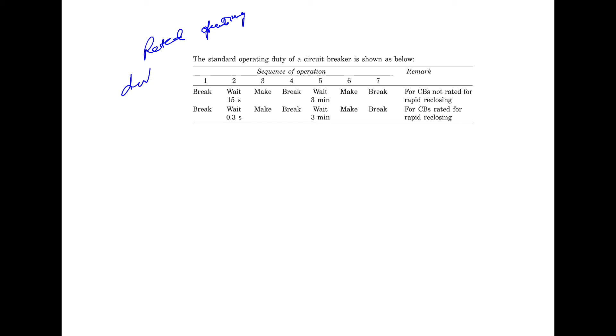Now the standard operating duty of the circuit breaker is shown here. First is break. This is for the circuit breakers not rated for rapid reclosing. What is the sequence of operation? It breaks, waits for 15 seconds, then it will make again, it will break, wait for 3 minutes, it will make, and it will again break. For the circuit breakers which are not rated for rapid reclosing, this is the rated operating duty.